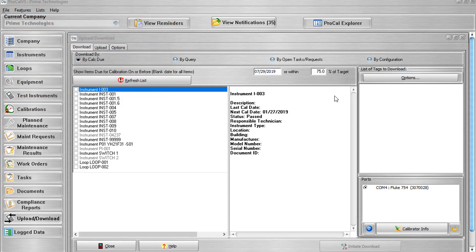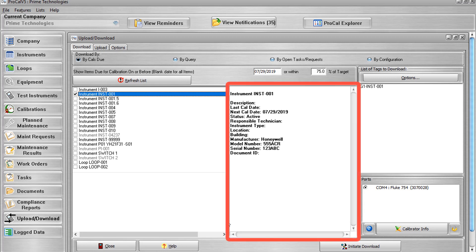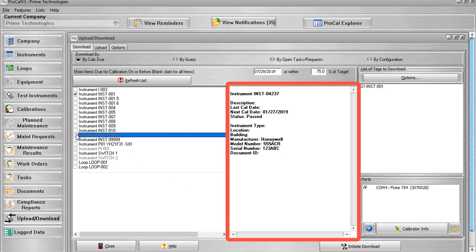We are on the Download tab, where you will determine which tags will be downloaded to the calibrator. There are four methods to choose from for generating a list of tags to download. The first is by Calc Due. This option gives you a list of instruments or loops which are due before or on the specified due date. Leave the date field blank to see all available items. To add an item to the list of tags to be downloaded, simply populate the checkbox next to it. Clicking on any item displays its information to the right of the checklist area. When a particular item cannot be added to the tag list, it is grayed out and unavailable for selection, and the reason it cannot be downloaded is displayed within the item's information.